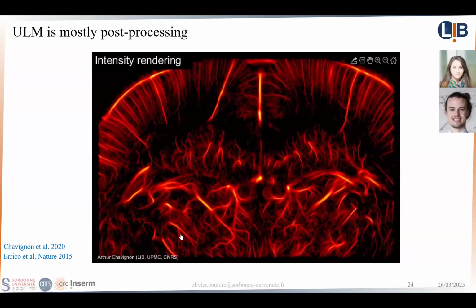A transducer is something that converts sound into electricity, or the reverse, electricity into sound. So when we send a pulse, in fact, we send an electric pulse. The electric pulse is converted into sound by the tiny little transducer. It propagates, then it's reflected from the structure inside. It comes back to the transducer. The mechanical wave gets converted by the transducer into an electrical wave, and then it gets read. So there's a transmit electric channel and there's a receive electric channel.